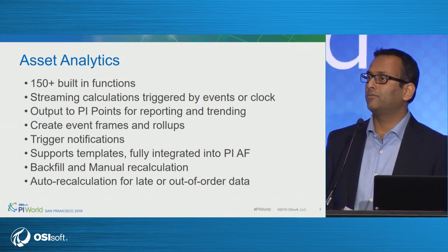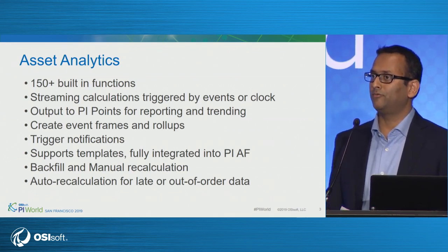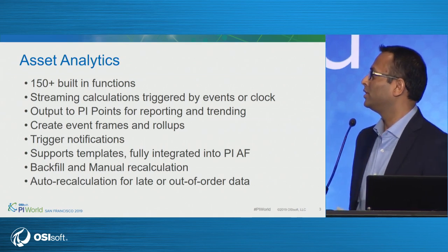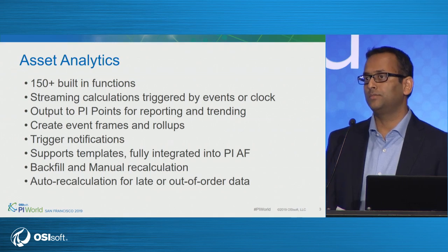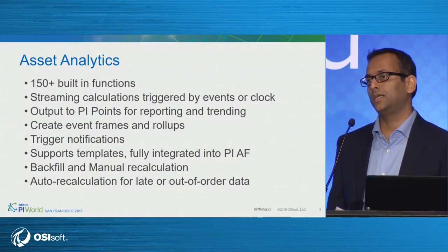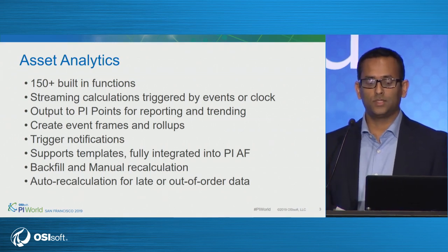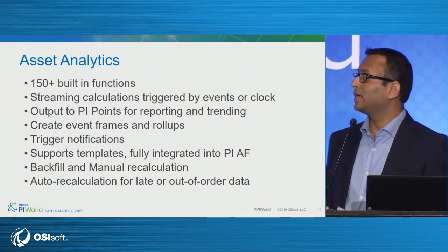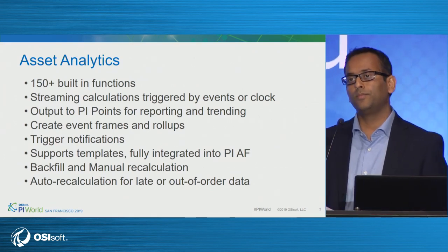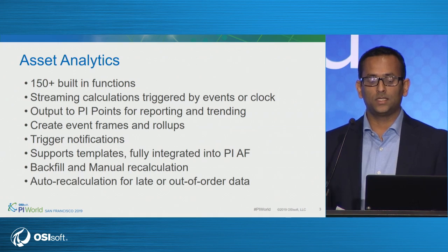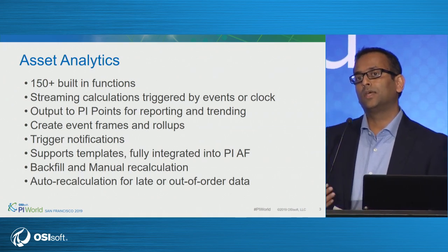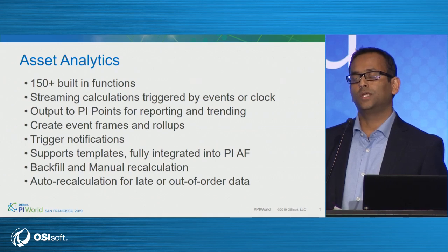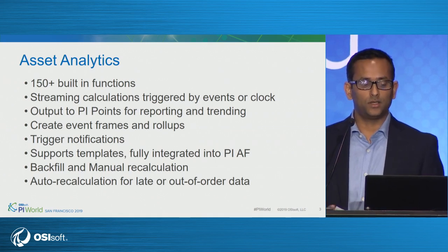We also have analysis types for generating event frames. You can use these for tracking downtime events or any other critical events in your system. You have to specify a start condition and end condition, and you get event frames and you historize those. You can also do aggregation type calculations, what we call rollup. And the other one I don't have on the screen is SQC. The event frames that are generated out of analytics, you can then use those to trigger notifications to get alerts.